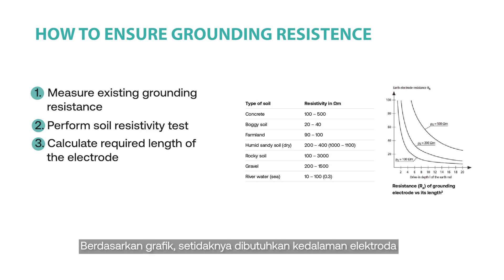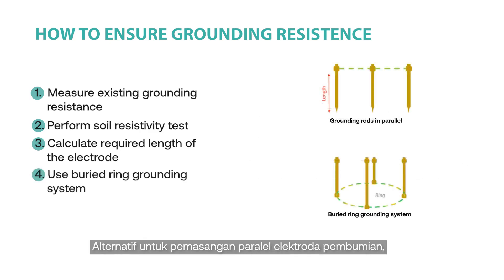From the following graph, at least 20 meters drive-in depth of electrode is required for concrete soil to achieve 5 ohms. Another solution is to install several rods in parallel. As an alternative to paralleling grounding electrodes, it is preferable to use a buried ring grounding system. Bare copper cable or copper-clad cable of at least 25 mm² could be buried around the powerhouse or PV array. A grounding box should be built to maintain the grounding connection as well as the soil condition.